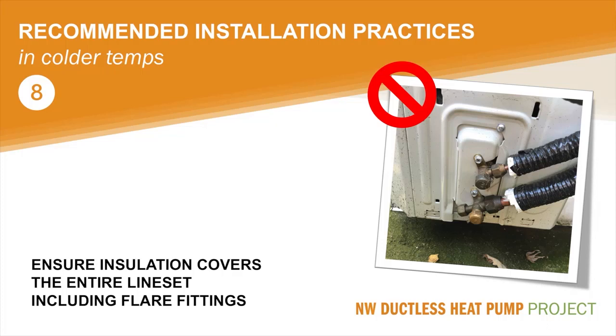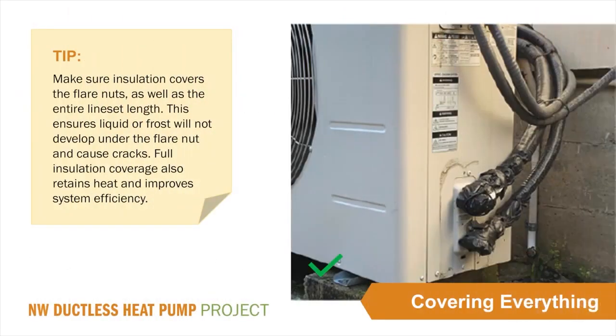We included this installation issue in our list because incomplete coverage of insulation on line sets is a widespread issue. While it is very rare that a flare nut will crack, it is worth bringing this to your attention because no one wants to see a ductless heat pump lose its refrigerant charge. Here is a great example of the practice we recommend. Notice how the insulation extends completely over the service valves and flare fittings. The insulation is further protected with UV blocking tape.